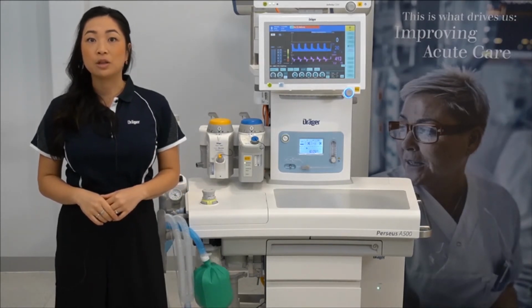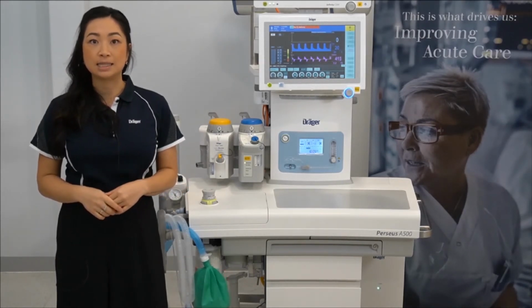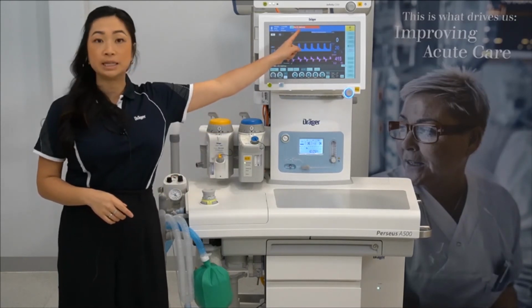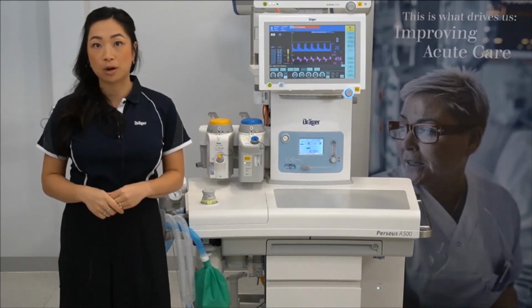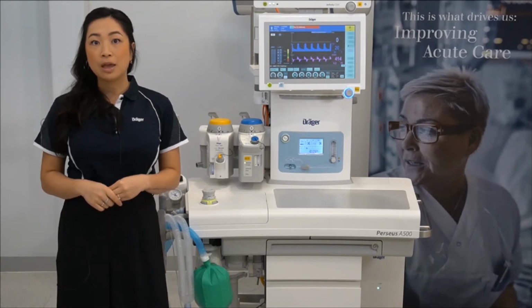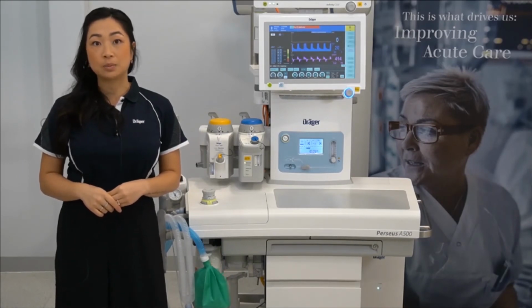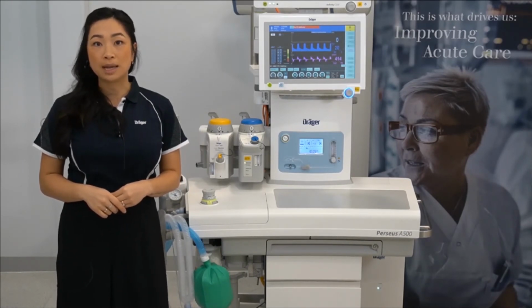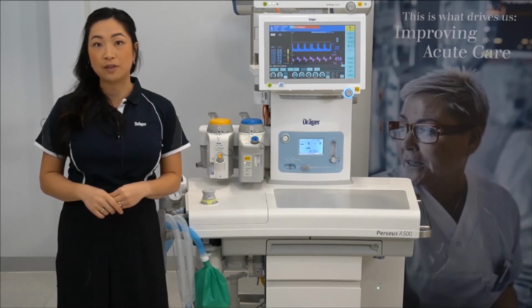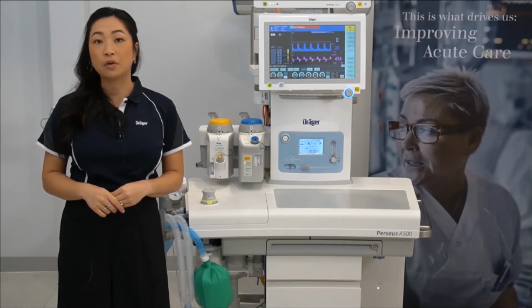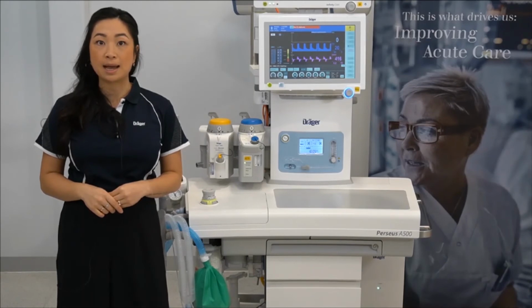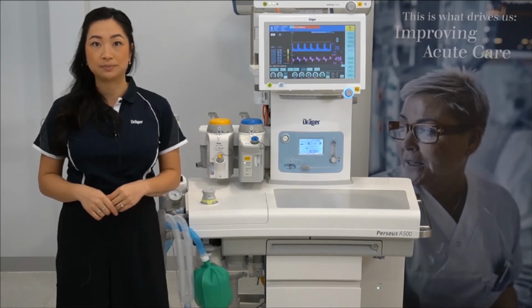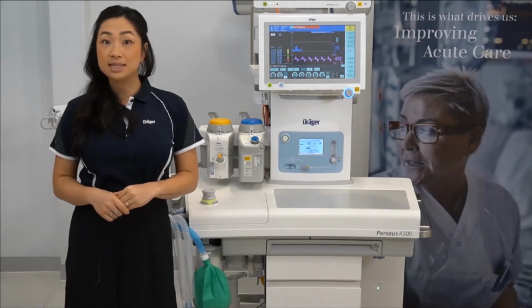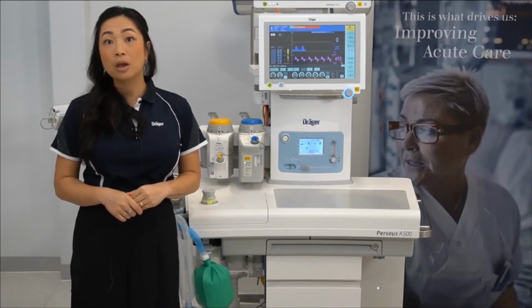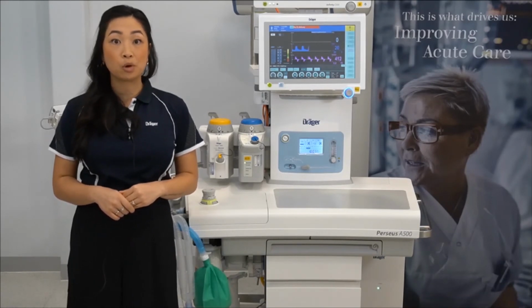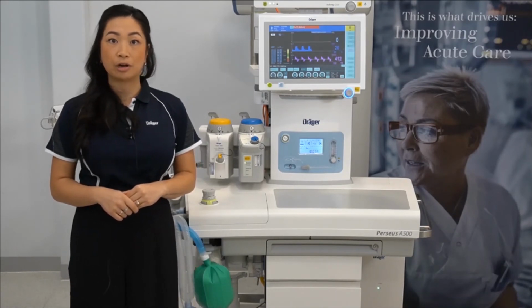Once you open your corresponding reserve gas cylinder, the high priority message will be downgraded to a lower priority. For users with advanced cylinder support, there will be the automatic conversion to your reserve gas cylinder supply. Therefore, the message will only appear as a blue advisory message. As your cylinder supply becomes low, the alarm message will become more prominent and increase in priority.